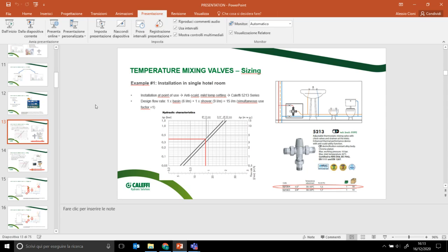Honestly speaking, we never face anti-scale failing because the valves are tested one by one, and the anti-scale, sorry, anti-scaled. Okay, so the prevention from scaling, from debris. I guess so, yeah. Okay, so the materials are engineered and tested in order to be resilient to scale formation. So they are tested in Caleffi labs for months in order to be smooth and always in good condition. Moreover, if you remind, we mentioned that these kind of devices have strainers and check valves at the inlet in order to protect the internal elements. So the valve can really face very serious and hectic conditions without any particular problem.